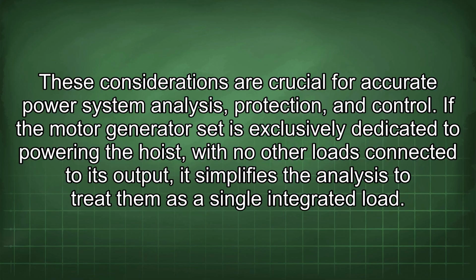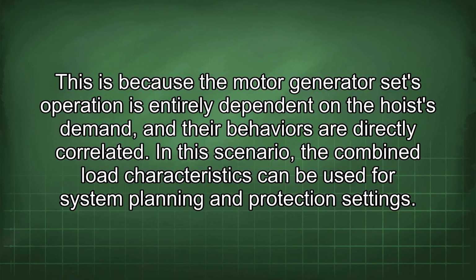If the motor generator set is exclusively dedicated to powering the hoist, with no other loads connected to its output, it simplifies the analysis to treat them as a single integrated load. This is because the motor generator set's operation is entirely dependent on the hoist's demand, and their behaviors are directly correlated. In this scenario, the combined load characteristics can be used for system planning and protection settings.